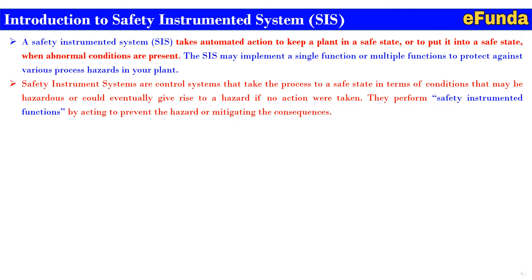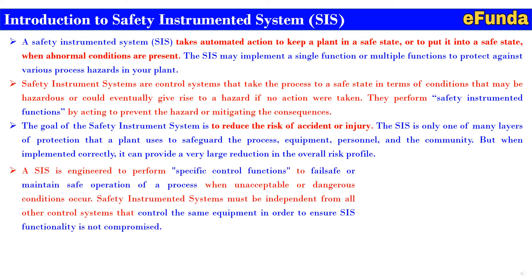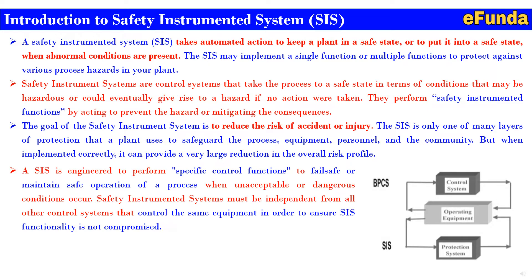The SIS performs safety instrumented functions by acting to prevent the hazard or mitigating the consequences. The goal of the SIS is to reduce the risk of accident or injury. It is one layer among many layers of protection that a plant uses to safeguard the process, equipment, personnel, and community. When implemented correctly, it can provide a very large reduction in the overall risk profile. The SIS is engineered to perform specific control functions to fail safe or maintain safe operation when unacceptable or dangerous conditions occur, and must be independent from all other control systems controlling the same equipment.